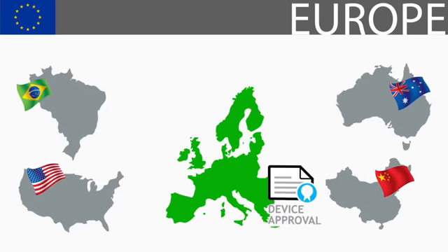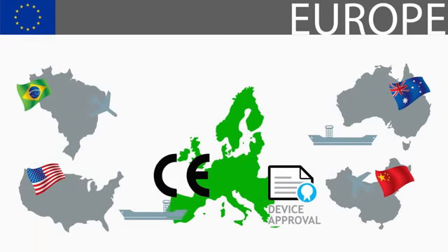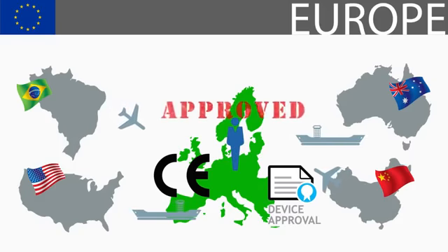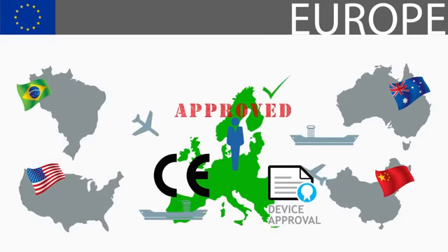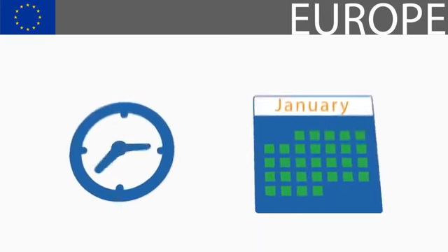Your CE marking certificate is issued for a certain period of time, typically 5 years, and remains valid for that duration, as long as you don't make substantive changes to the product, claims, its intended use, and your yearly surveillance reviews are successful. So how long does it take to get approval in Europe?